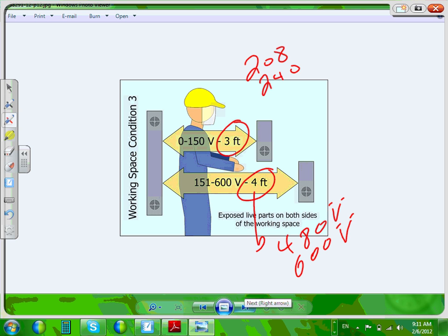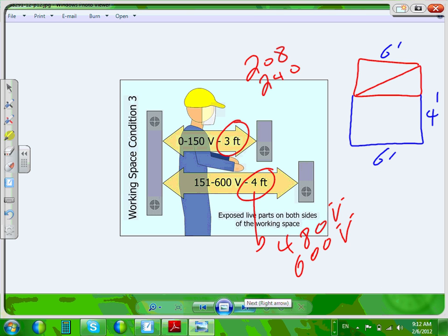A lot of us in the engineering community, guys, you know what we do? We always put that 4 feet, no matter what, in front of the equipment, even if it's 208. So you draw in front of the equipment. If this is my equipment right here, that's my equipment. What I do is I draw a 4 foot square in front of it. This is 4 feet. Let's just say this switch here was 6 feet. 6 feet wide, and I hash that area. And I say this is a sacred cow. This panel is 6 feet wide, and the depth is going to be 4 feet, regardless of the voltage, just to keep the space. Any question, guys? Because 4 covers the worst scenario.